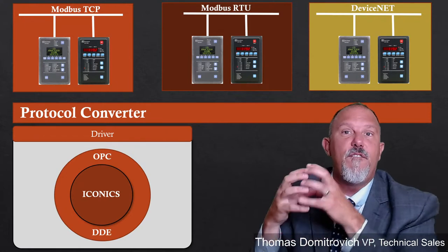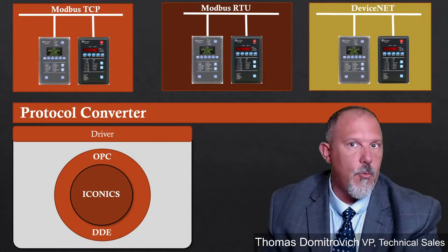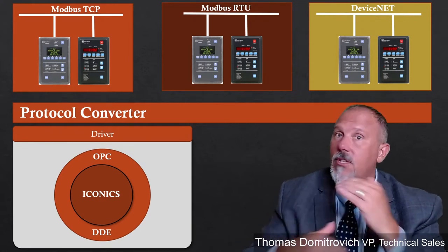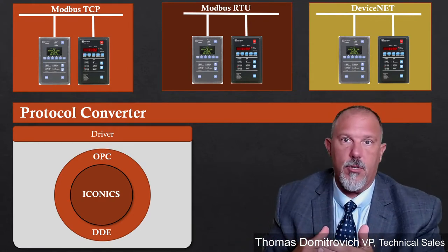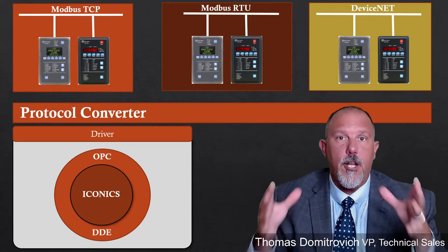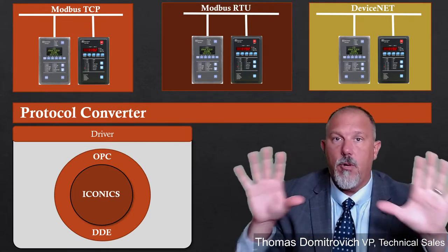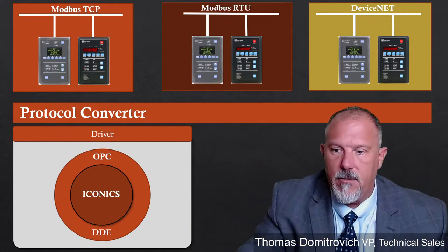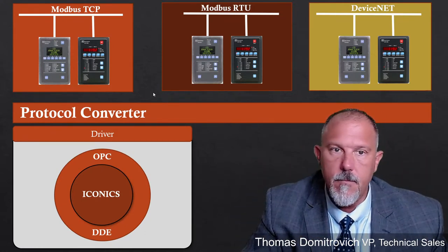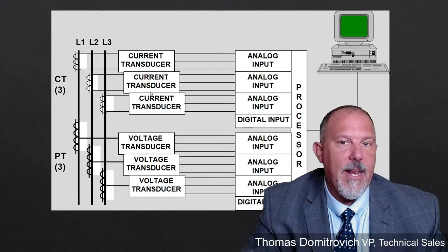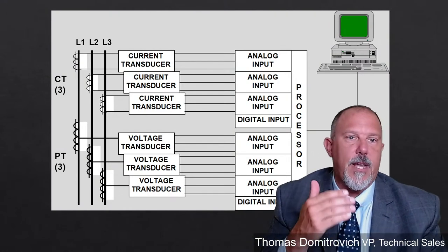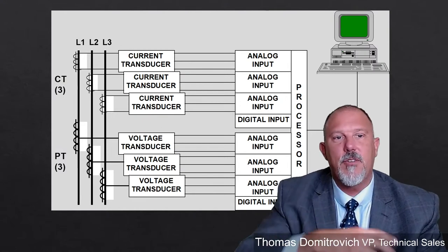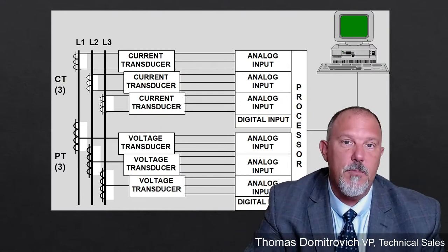You're not dealing with a file structure like maybe a waveform would be, or logged data. This would be real-time exchange of parameters that I can display on a human-machine interface like Wonderware, where I could have a one-line diagram and it can show me my voltages throughout the power distribution system. I have a processor, I have analog inputs, I can take currents into current transducers, into a microprocessor, and then pull that information into a computer.